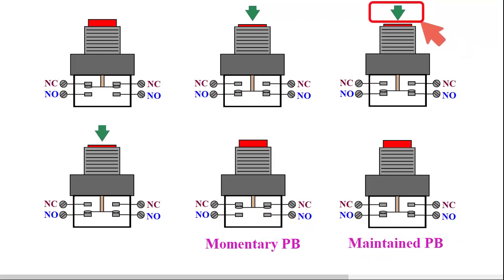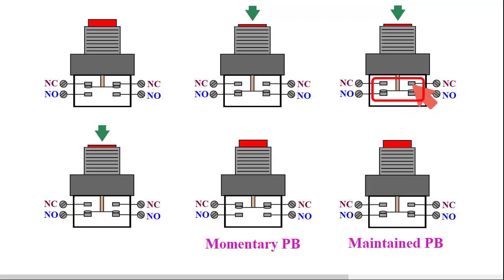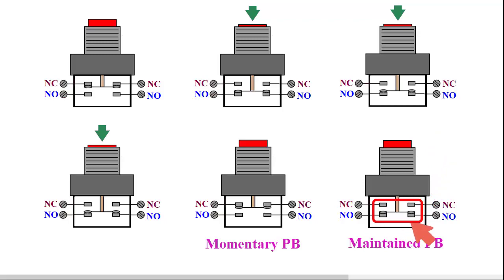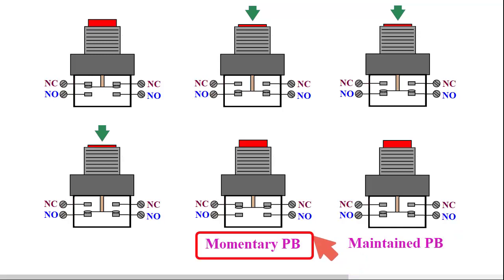For a maintained push button, when pressure is applied, the normally closed contact becomes open and the normally open contact becomes closed. When the pressure is released, the contact behavior does not return to normal — it maintains the condition just as when it was pressed. Normally, switches used in homes for lights and fans are maintained type. In industry, momentary push buttons are normally used to run motors, fans, lights, and other devices.